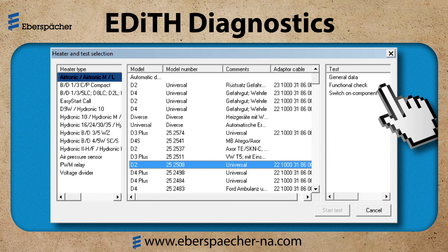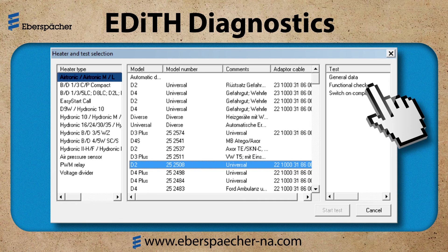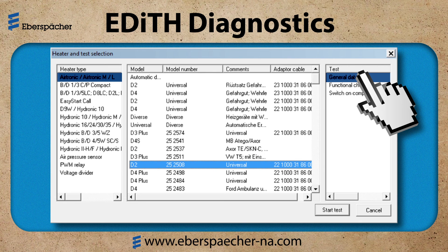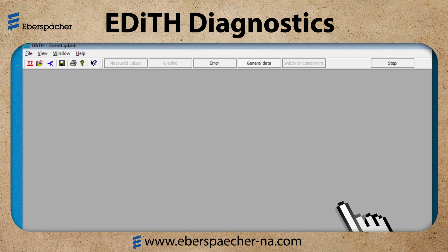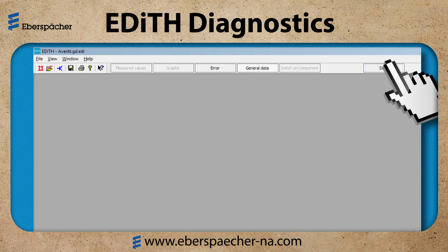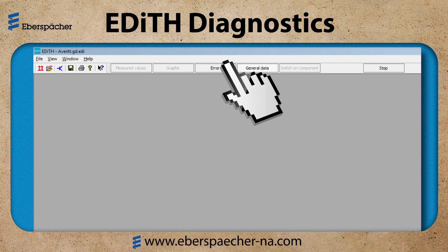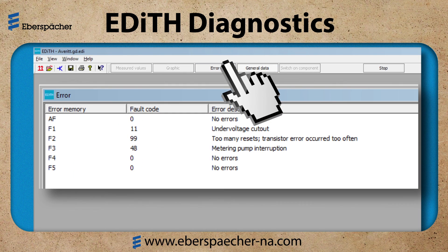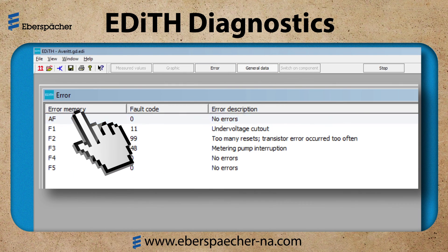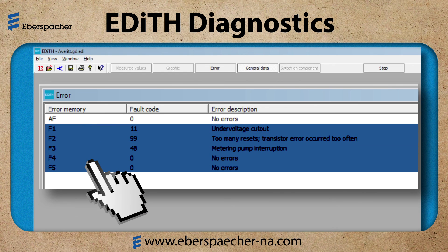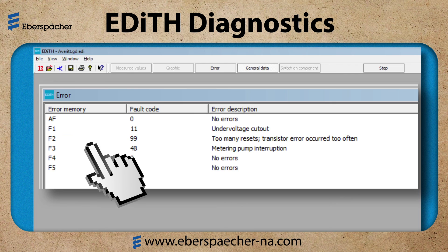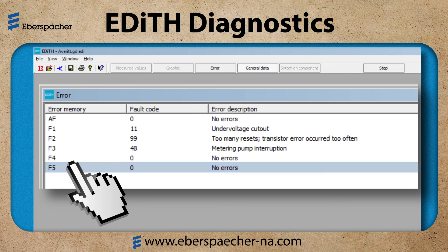The first thing I'm going to do when working on a heater is the visual inspection, then I will connect EDITH Diagnostics and perform a general data test. Select the test and click on start test. The tabs in black are available during this test. First, we will look at the error tab. This shows the AF active fault and the historic fault codes, F1 through F5. F1 is the most recent and F5 the oldest.